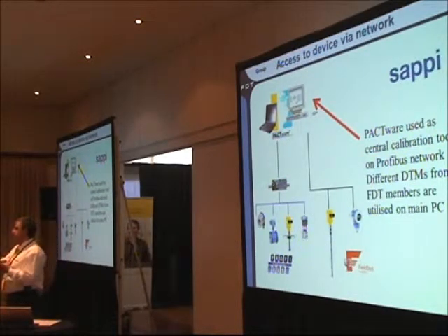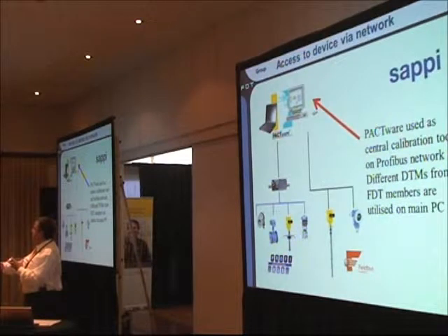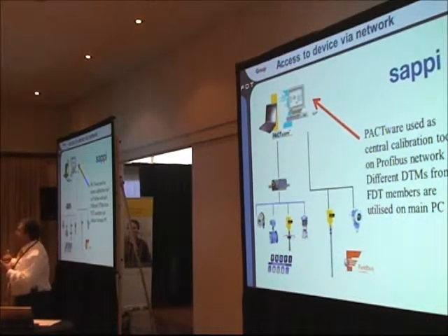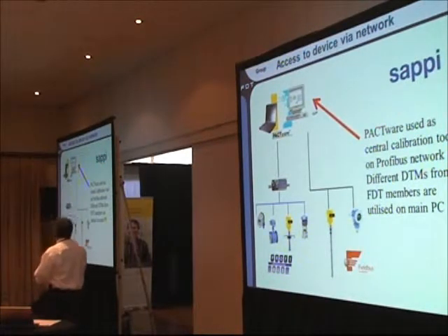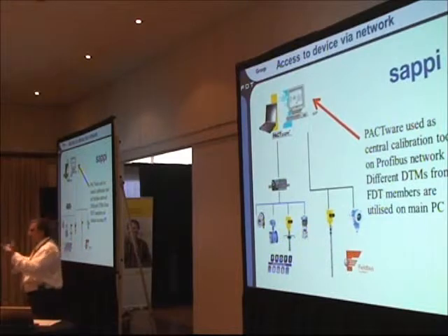Interesting in Profibus, and also Fieldbus Foundation, is that the status information comes automatically with the measuring value. The measuring value comes to the DCS and it automatically gives you the status too. With HART, you have to ask the device for its status, so it's a little bit slower since you have to ask for that. The bus systems normally give you all this in detail automatically.